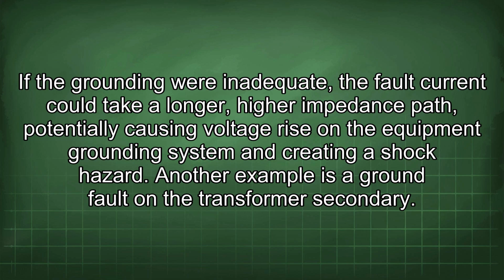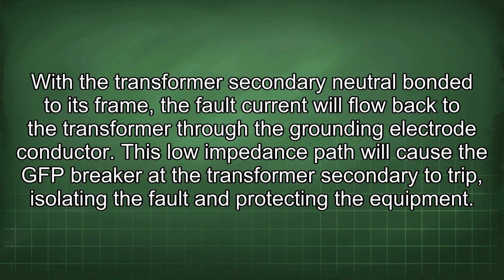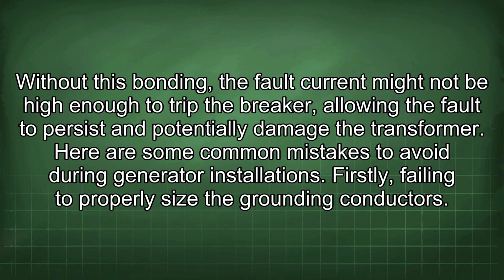Another example is a ground fault on the transformer secondary. With the transformer secondary neutral bonded to its frame, the fault current will flow back to the transformer through the grounding electrode conductor. This low impedance path will cause the GFP breaker at the transformer secondary to trip, isolating the fault and protecting the equipment. Without this bonding, the fault current might not be high enough to trip the breaker, allowing the fault to persist and potentially damage the transformer.